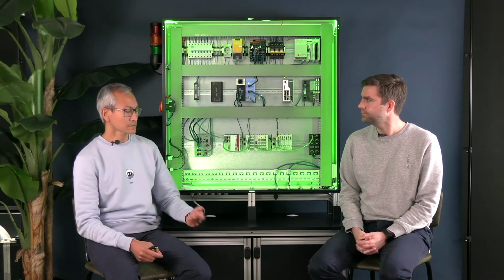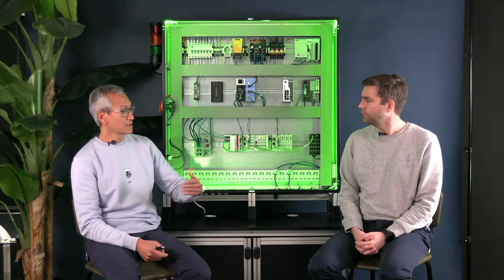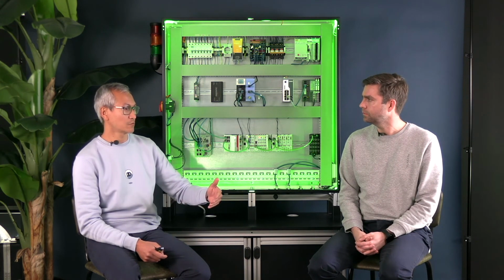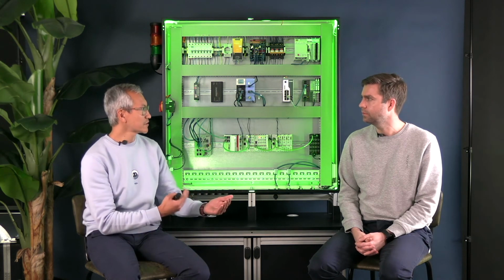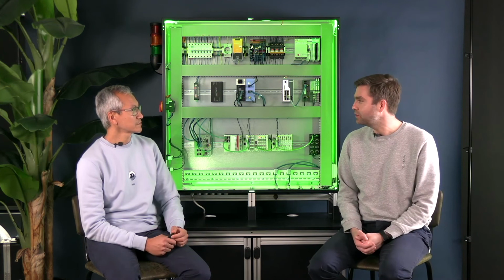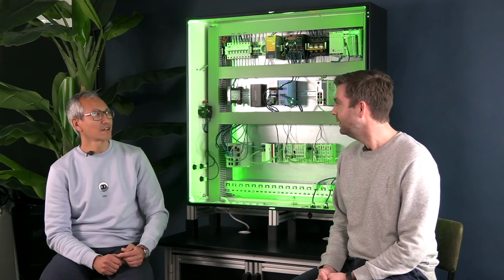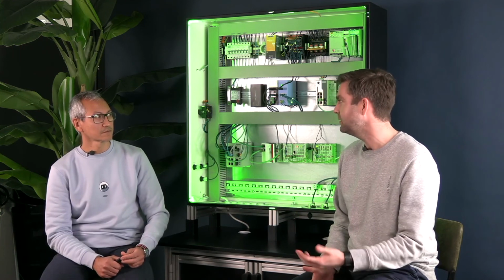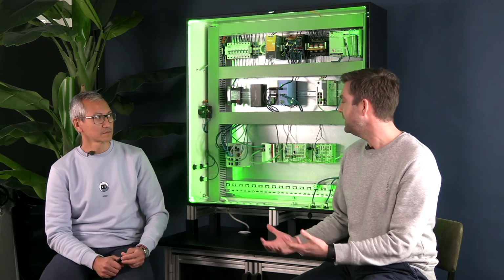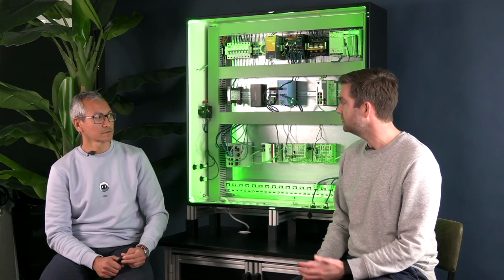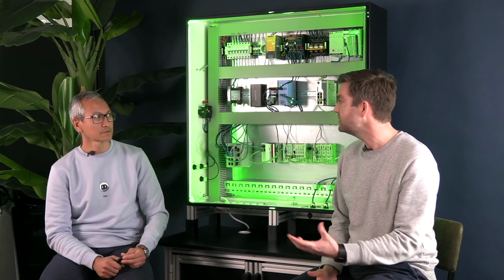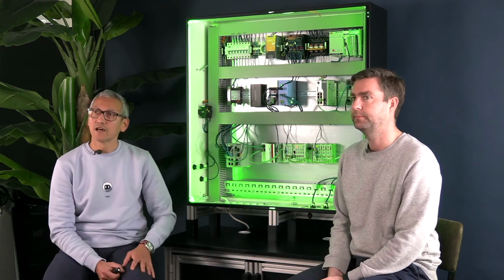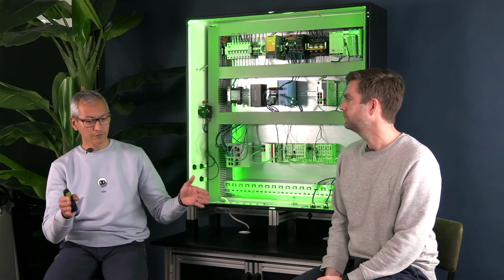Firmware differences is something you can especially see during Ethernet operations, because you have a lot of different types and different versions of PROFINET also. Yes, it's been developed already for 15 years. But it's continuous. I always know that when I talk with our support, the first thing they always ask is, have they updated the firmware? And with our latest launches, we have groupings. Managing this kind of information is made easy by the grouping feature, which enables you to focus on specific devices that are critical in your network or critical to your ring. Exactly. And it's not necessary that you have the latest version, but that all versions are equal.